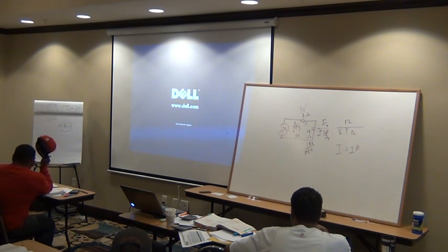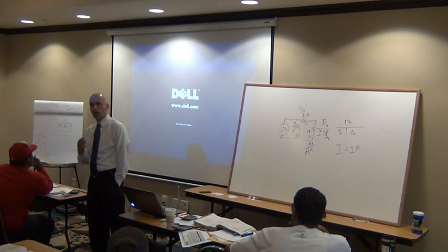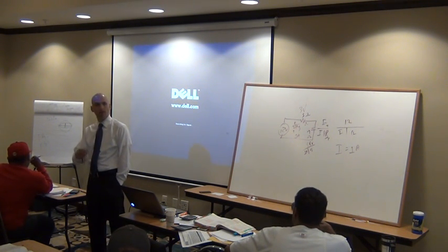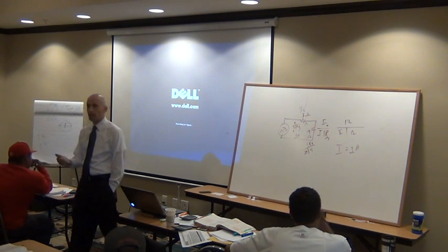And then it's simply, you find that insulation type, and then find the wire size, and all the way on that far right-hand side, there's your value for an individual conductor. And if you have 8 of whatever it is, you just multiply that times 8 and then go on throughout the list of whatever wire insulation types you have.